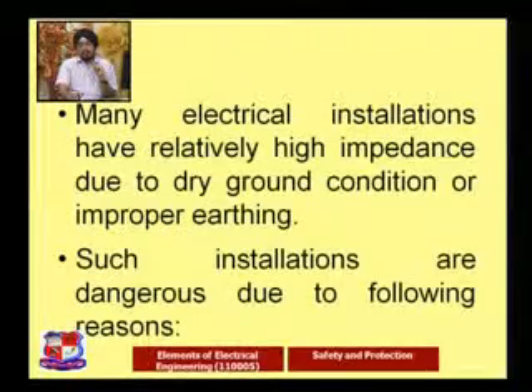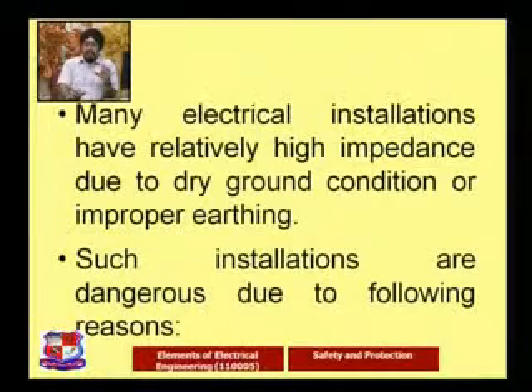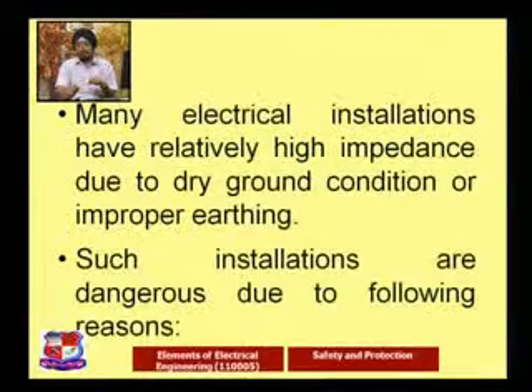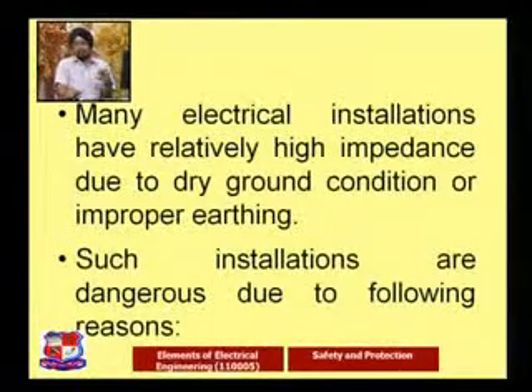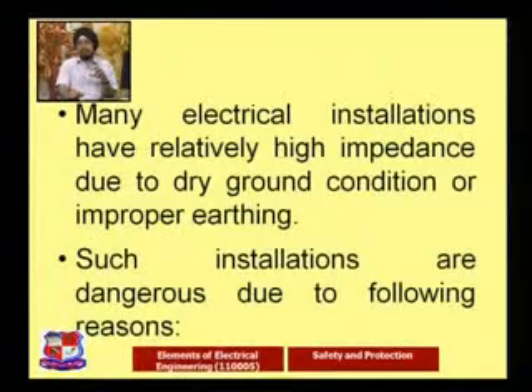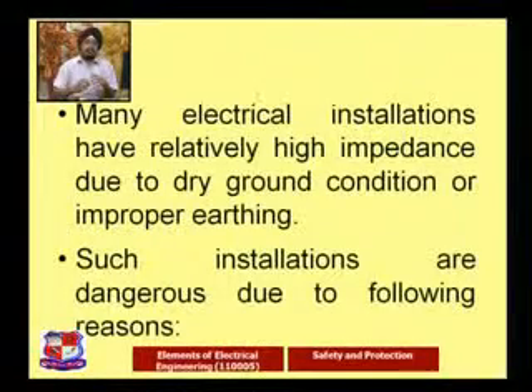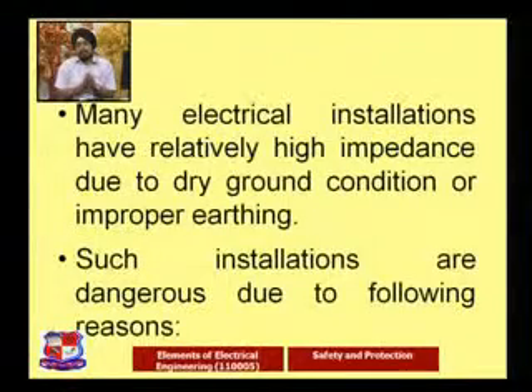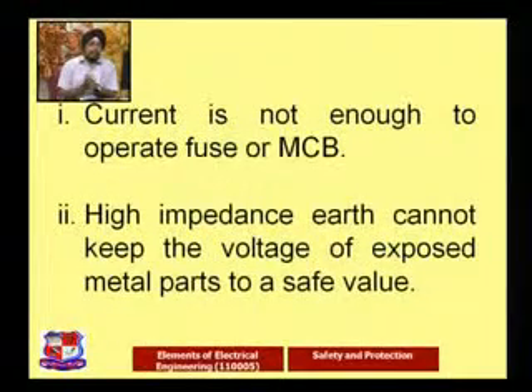Why do we require it? Many times we do an installation, but we don't know the soil condition. It is important to know the soil condition, which we discussed in the previous session on grounding. So we don't know the grounding condition. If the grounding condition is not proper, the earthing is never going to be proper. Such an installation, where the earthing is not proper, is dangerous, it can cause problems. Now, there can be two types of dangers.